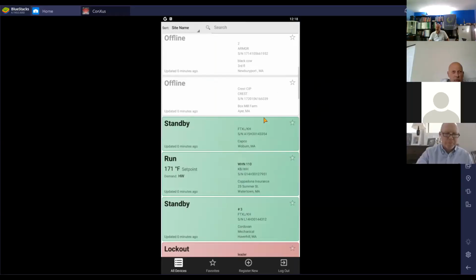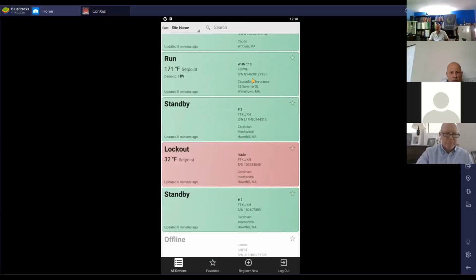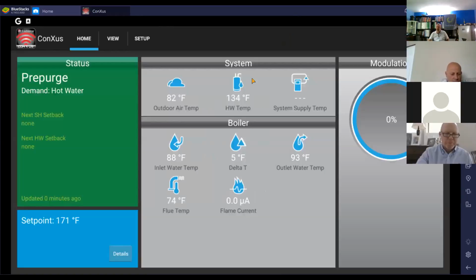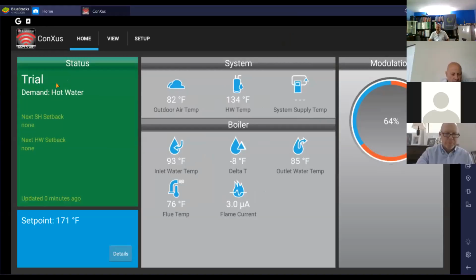Let's go. Oh, this guy's running right now here. There we go. So this boiler's got a call for domestic hot water. We just fired, it's at 64% right now. Here's my domestic water temperature at 134 degrees. You can see right now that the water is cold in the boiler. It's cool right now, coming in at 92, going out at 89.